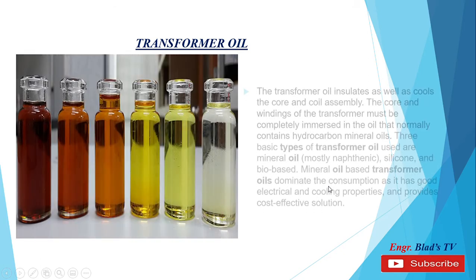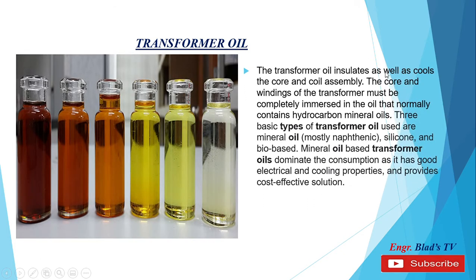Transformer oil. The transformer oil insulates as well as cools the core and coil assembly. The core and windings of the transformer must be completely immersed in the oil, which normally contains hydrocarbon mineral oils. Three basic types of transformer oil are mineral oil, silicone, and bio-based. Mineral oil-based transformer oils dominate the market as they have good electrical and cooling properties and provide a cost-effective solution.